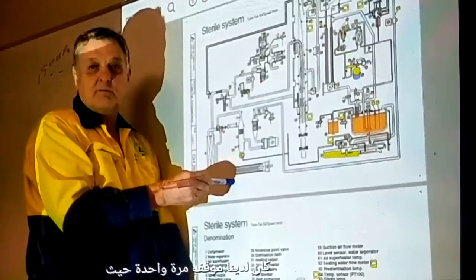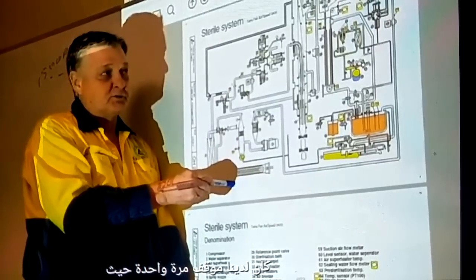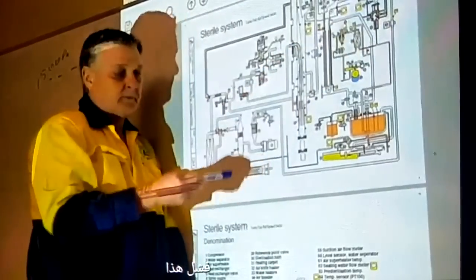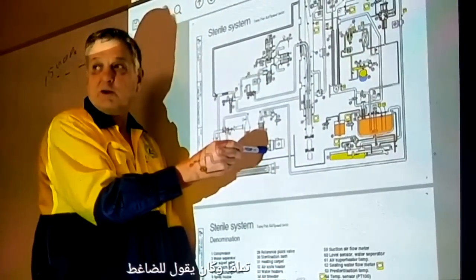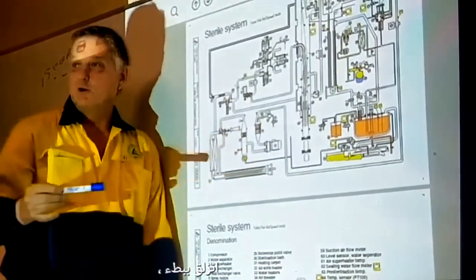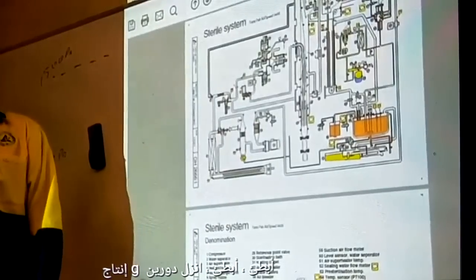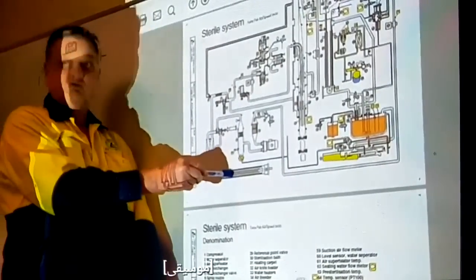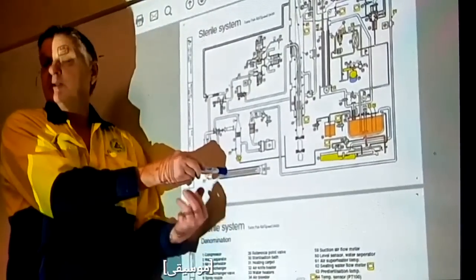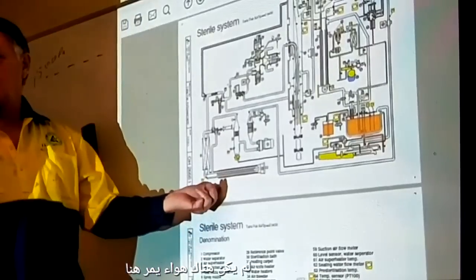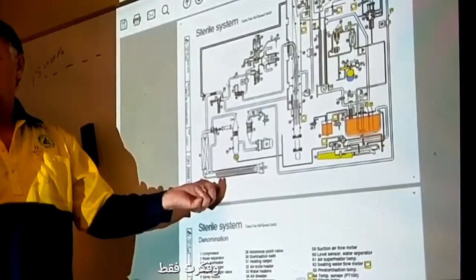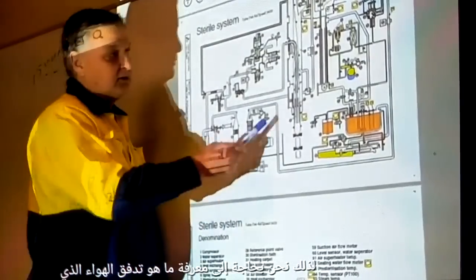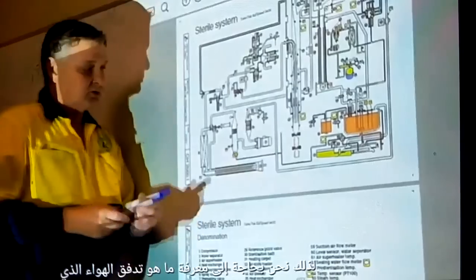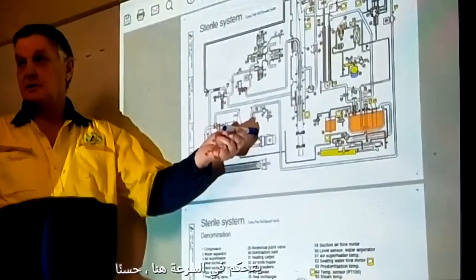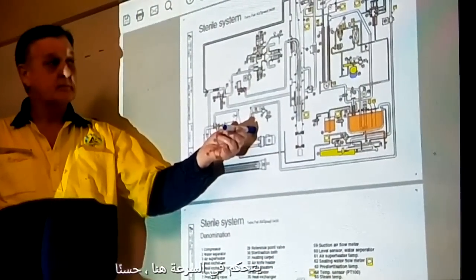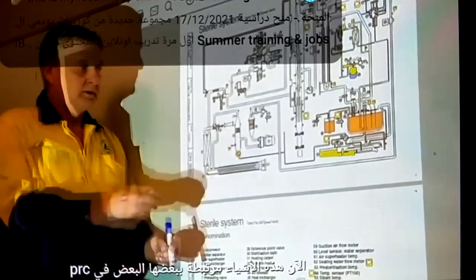We had a situation once where this failed completely. And it was saying to the compressor, slow down, slow down, slow down, during production. So there was no air going through. And it just blew up. So we need to know what the airflow is to control speed. So these are tied together.